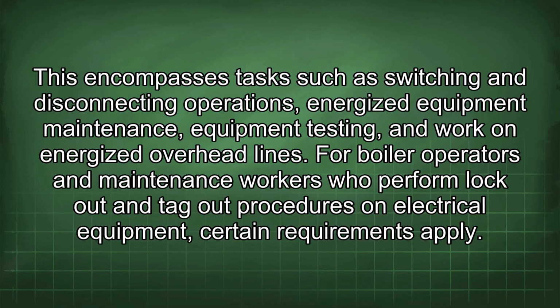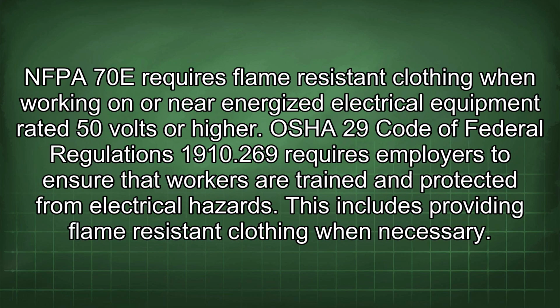For boiler operators and maintenance workers who perform lockout and tagout procedures on electrical equipment, certain requirements apply. NFPA 70E requires flame-resistant clothing when working on or near energized electrical equipment rated 50 volts or higher. OSHA 29 Code of Federal Regulations 1910.269 requires employers to ensure that workers are trained and protected from electrical hazards. This includes providing flame-resistant clothing when necessary.